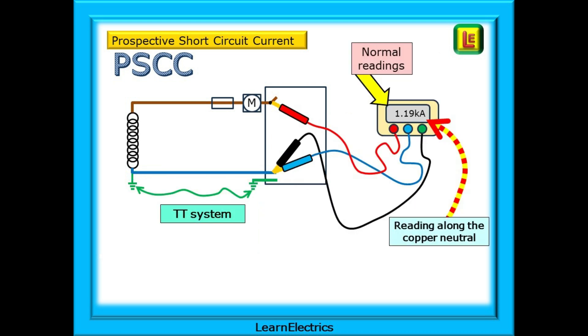As you would expect the same settings are used for TT systems but this is TT with a high impedance to earth. Then how come the PSCC reading looks normal, about the same amps as the TNCS and TNS systems? Why was PFC just 3 amps and now PSCC is 1190 amps? This is because the neutral is a copper cable all the way back to the transformer. It is not relying on an earth connection. It is not using the soil. So we should expect readings anywhere from a few hundred amps up to one kiloamp or more.